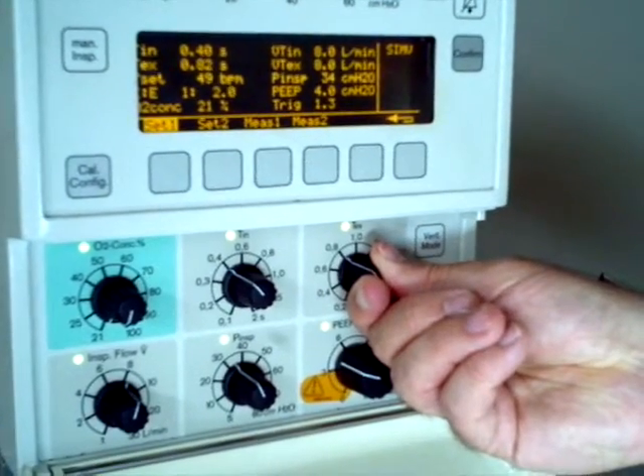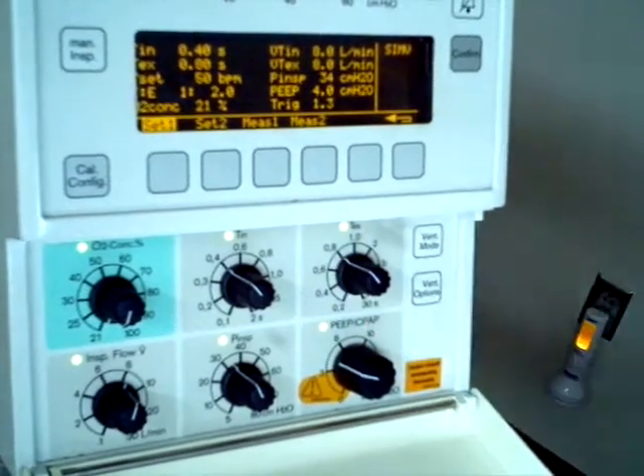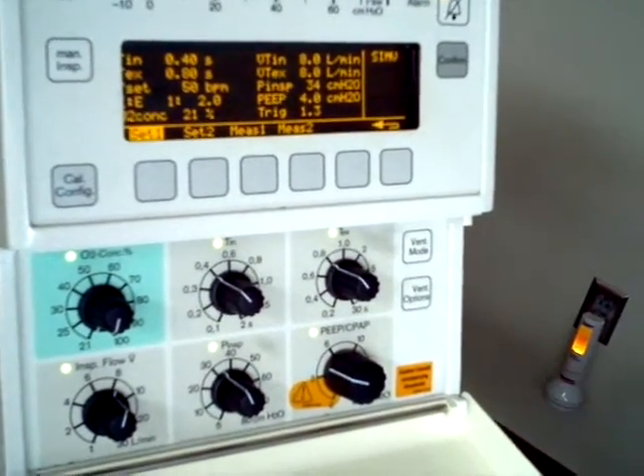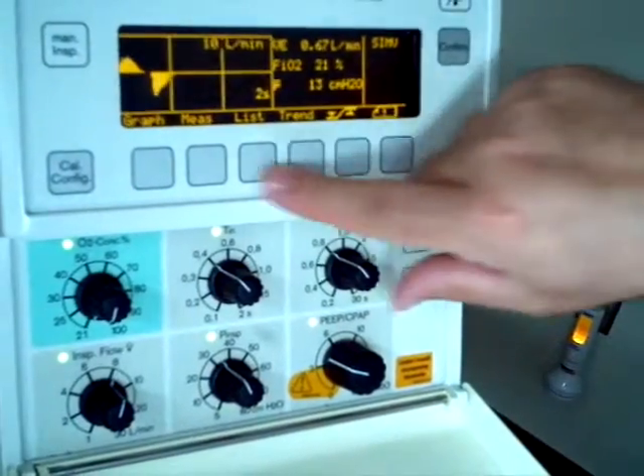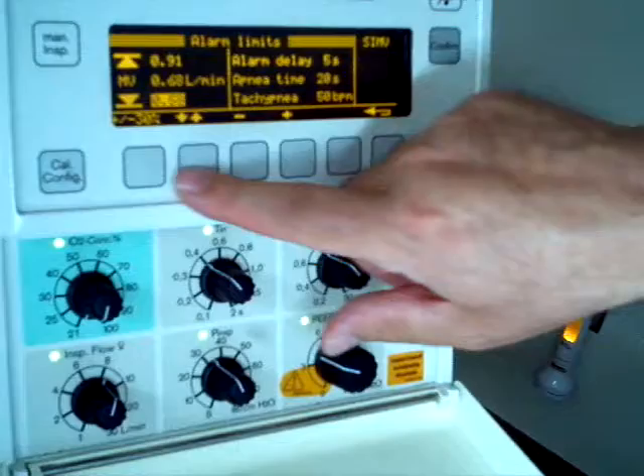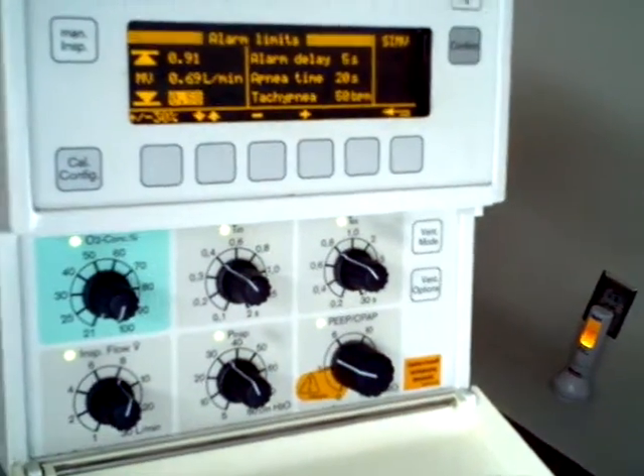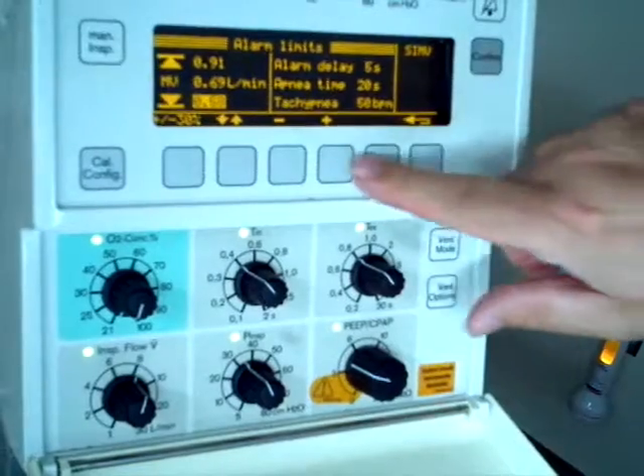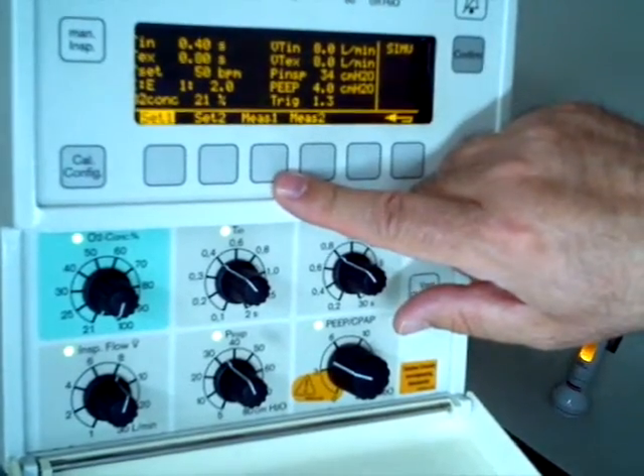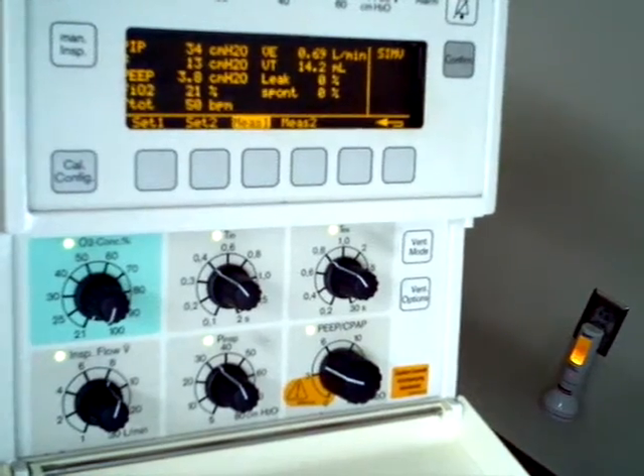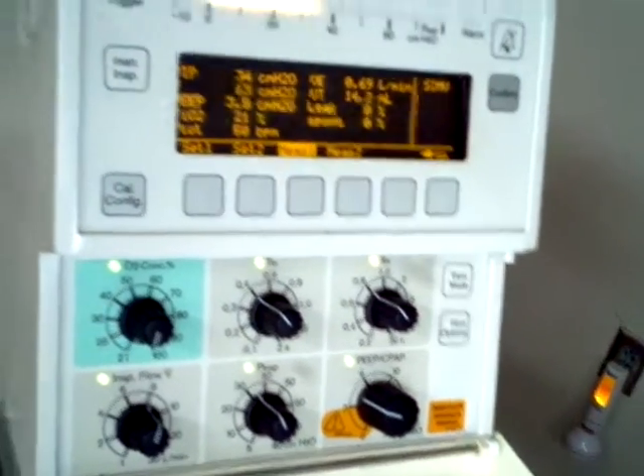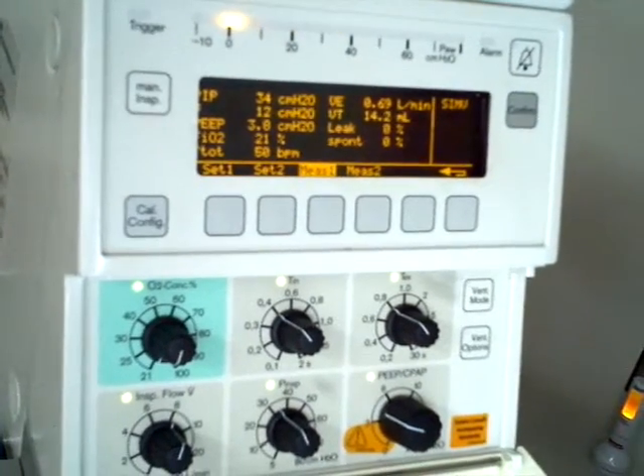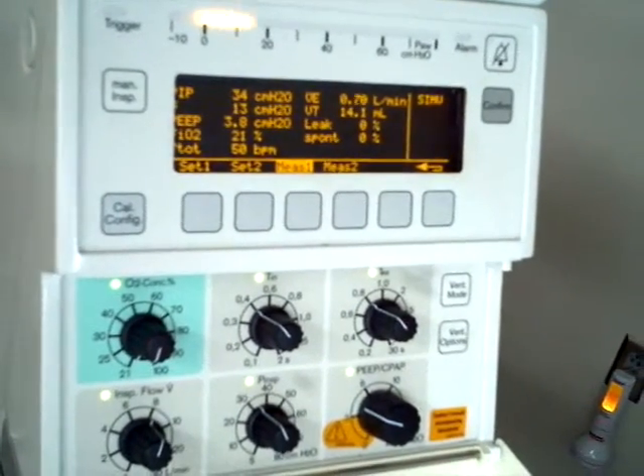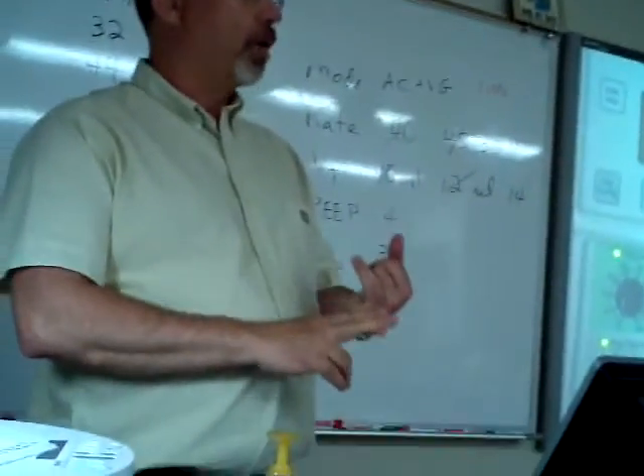Again, I'm going to get that perfect too. So now I have a rate of 50. Let's go back. Notice I have a little gap there now, and alarms are about the same. How's my tidal volume? 14.2. Could go down on a PIP just a hair if we still want 14. If you need to go back and look at a card, that's fine. Typically you're not going to change anything unless I tell you to. Check your tidal volume frequently to make sure it's set right.